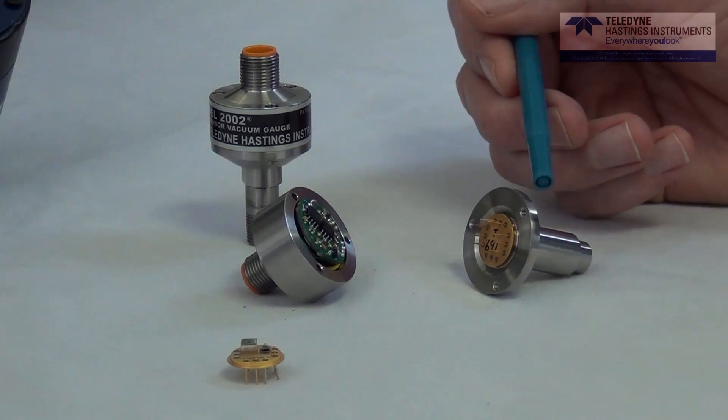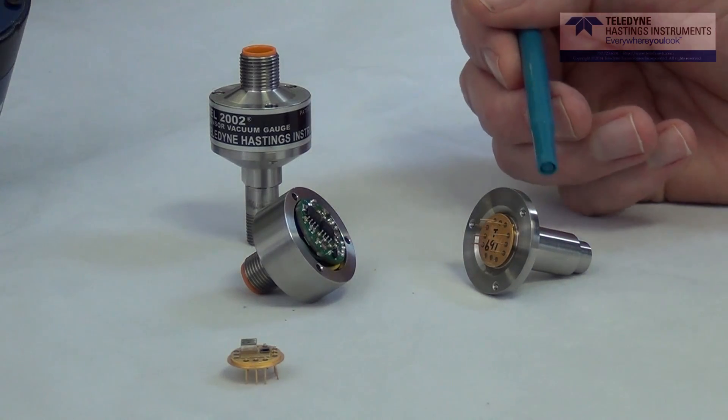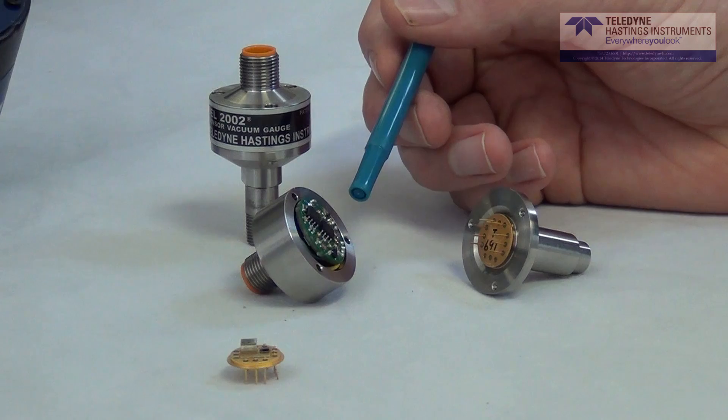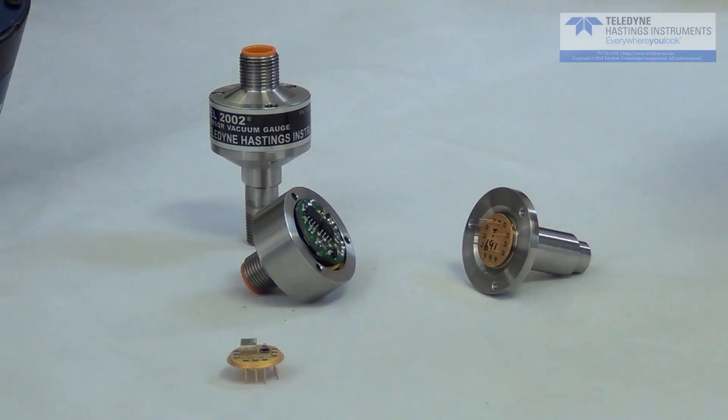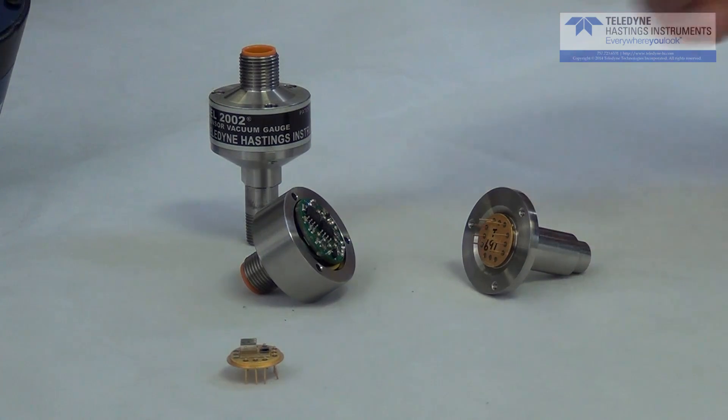So our next step is to take this sensor tube stub assembly and couple it to the cap assembly shown here. Now the cap assembly includes a small PC board that helps to operate the two sensors. But one of the best features of this arrangement is an EEPROM memory chip which stores the calibration information about each tube.